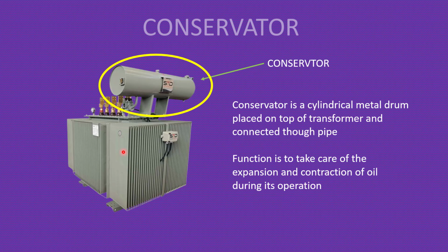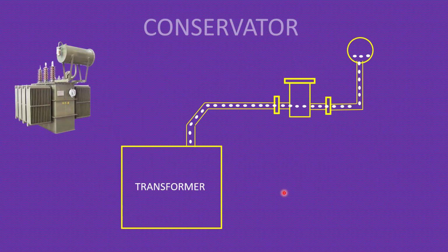We know an oil-filled transformer is filled with oil. This oil provides insulating properties as well as cooling. This transformer oil should not be in touch with moist air. If moisture comes in touch with transformer oil, its insulating property weakens and there is a chance of some acidity formation also. So this will weaken the insulating as well as the cooling property of the oil. In order to avoid that, we are using a conservator. The transformer is filled with oil in such a way that the conservator is also partially filled.